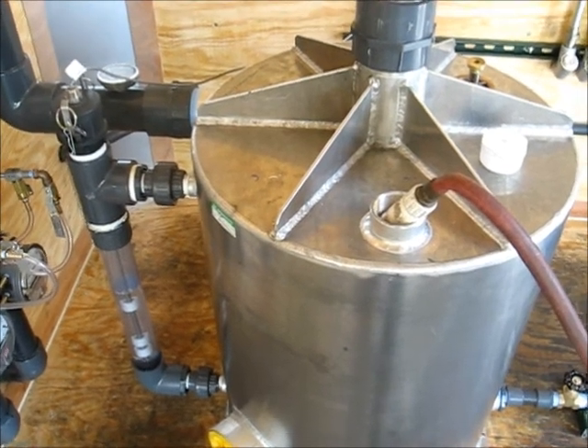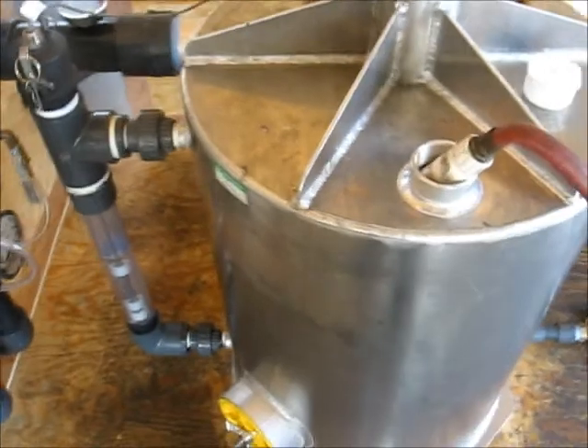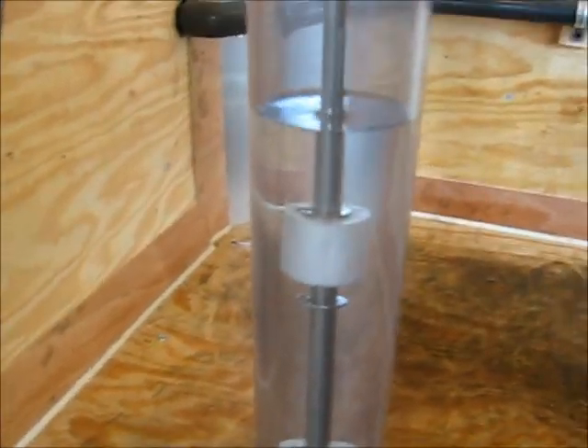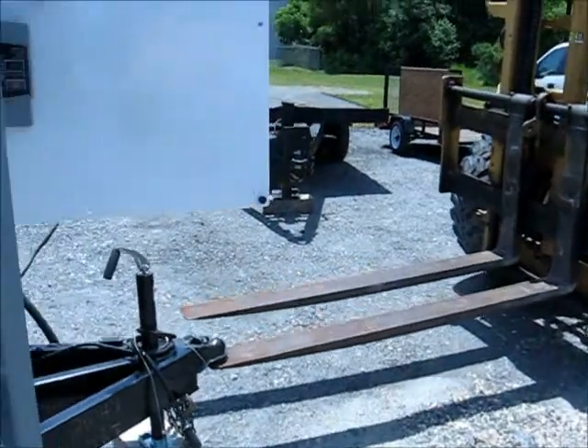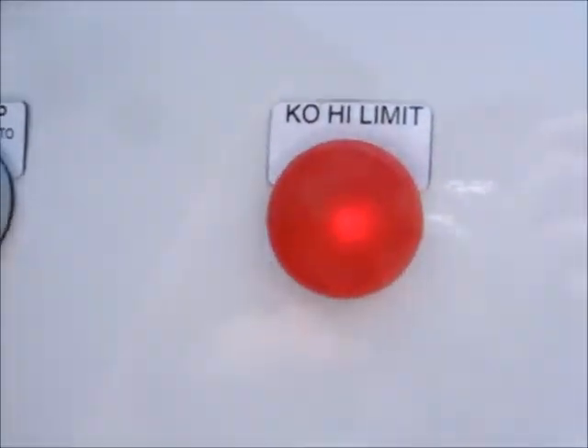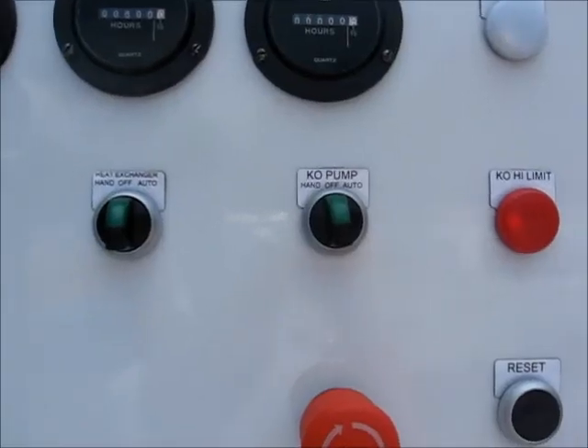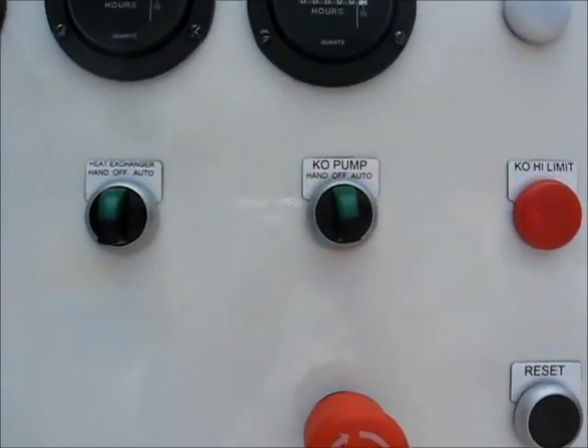We filled our knockout tank with water through the vacuum relief valve port using that garden hose. You can see it's above the high level float. So we're going to walk over to the control panel and show you the alarm light. There. KO high limit is lit. Alright, the knockout tank's full of water. We're going to put the knockout pump in auto.